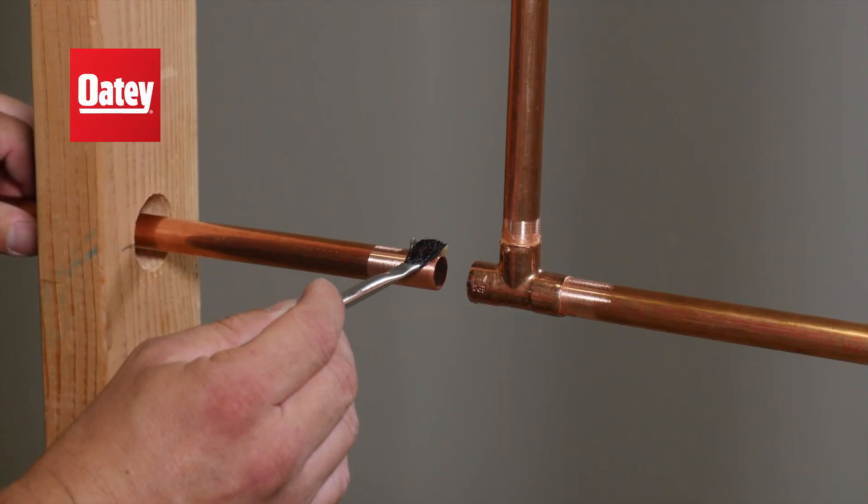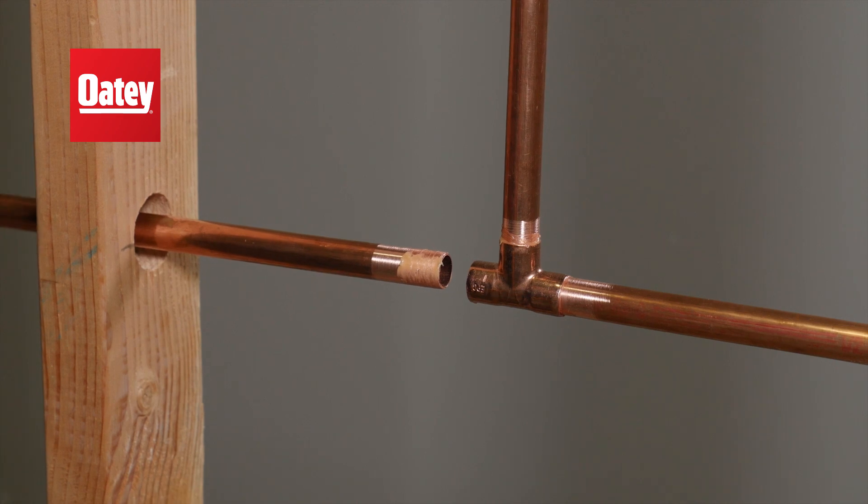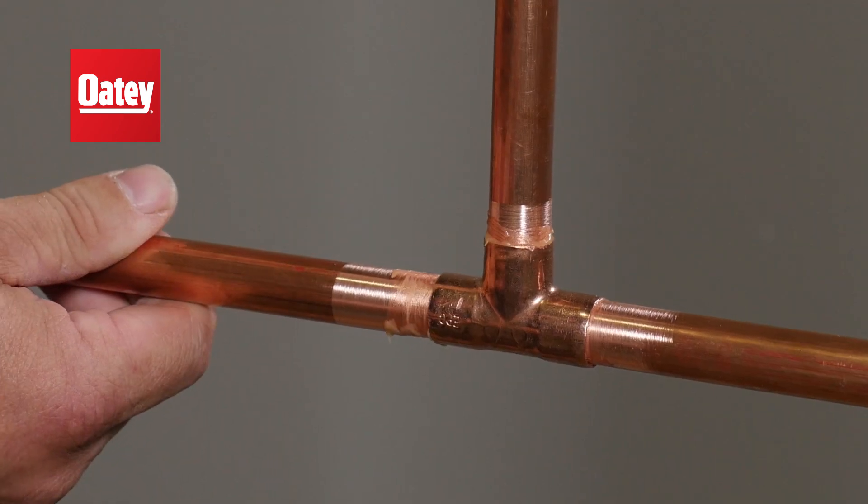Apply a light coating of Oatey Flux to the pipe end and fitting hub with an acid brush. Remove any excess, then push the pipe into the fitting hub.